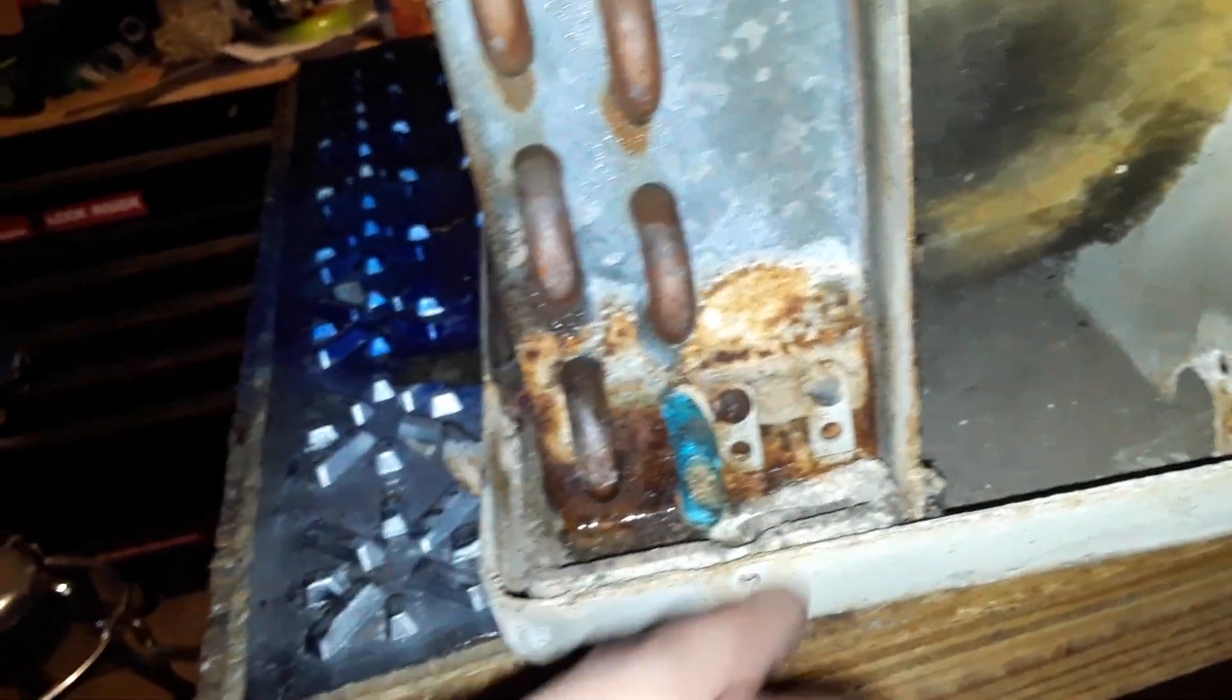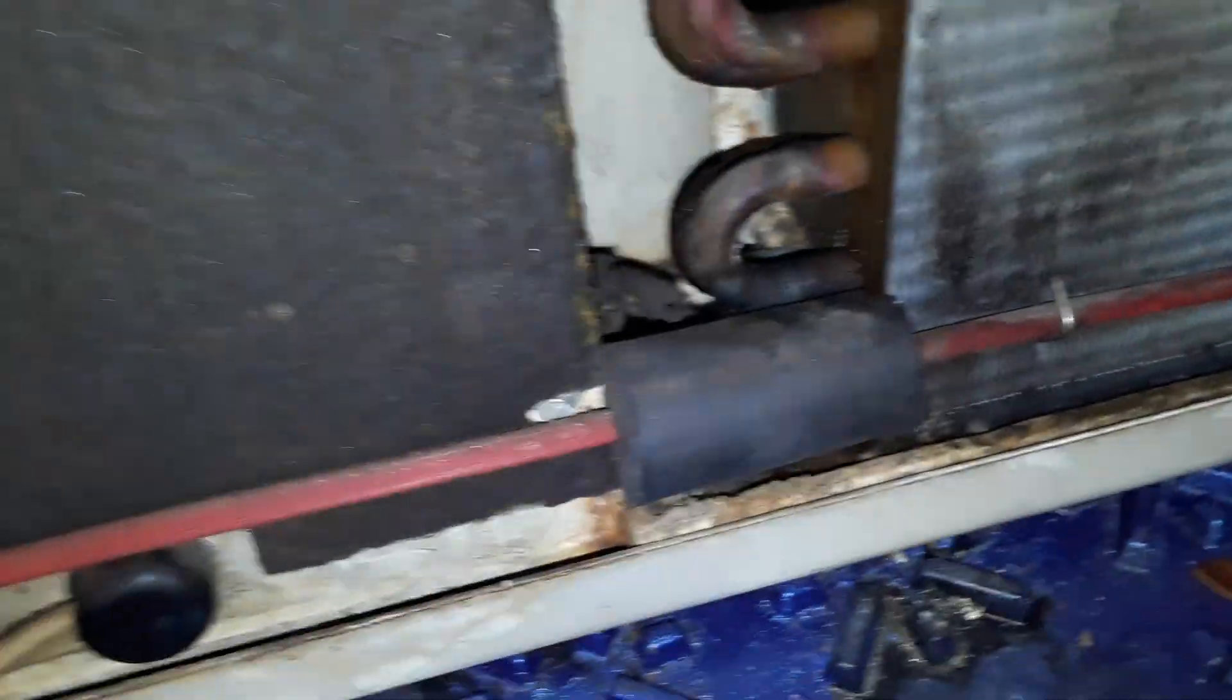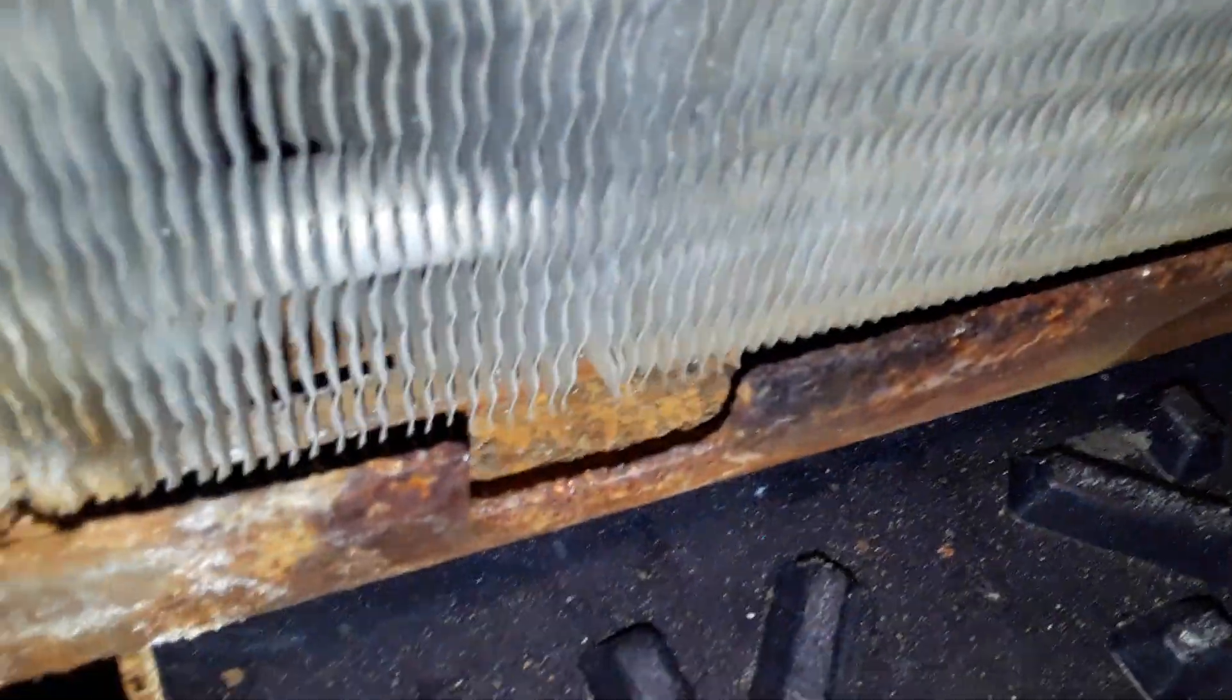I was looking at this at first thinking this is going to be difficult to take apart, but actually it doesn't look too bad. I'm still second guessing - let me think about this. It looks like the evaporator gets held on to the chassis by these two pieces of steel that come up on both sides. This whole piece sits in there and floats, so it looks like this disconnects and comes up. The whole fans and everything come out in one piece like that Admiral over there, so everything comes out in one piece. You have the cooling system attached to the base pan. This is smart because the way they did it, they have it elevated about a quarter inch off the bottom of the base pan, which is great. It really helped with keeping the steel work clean on the bottom.